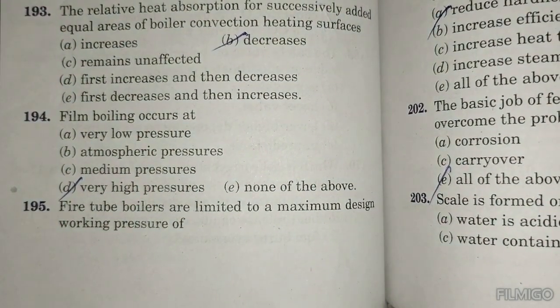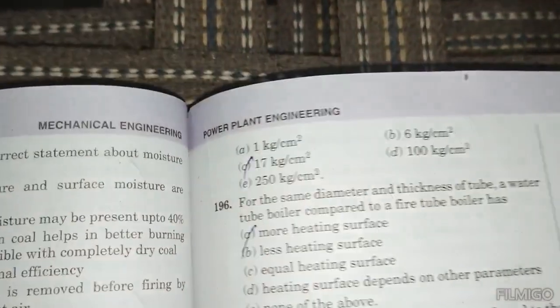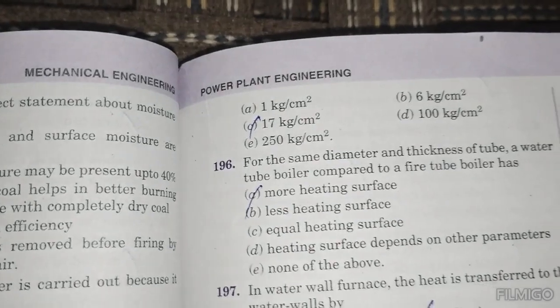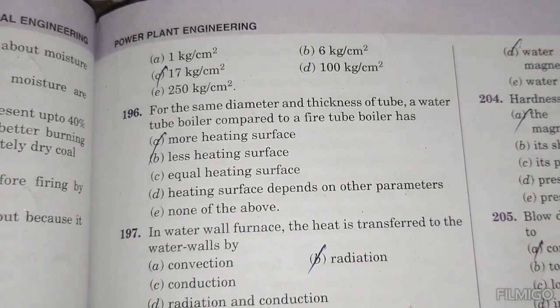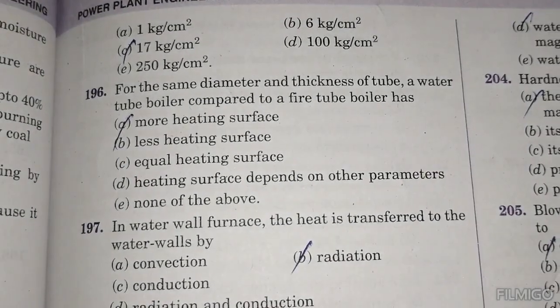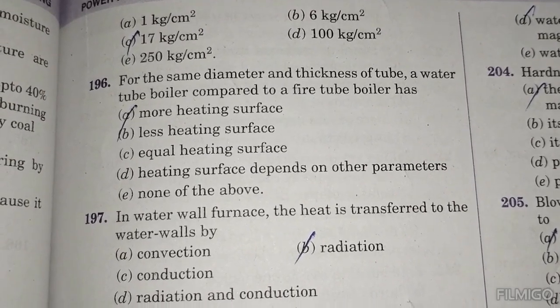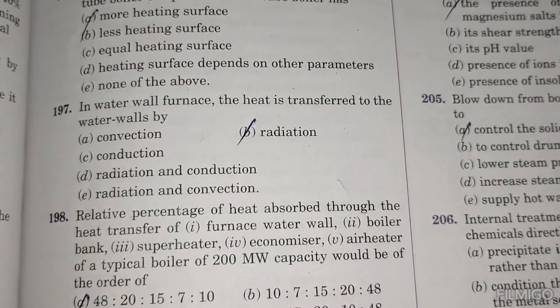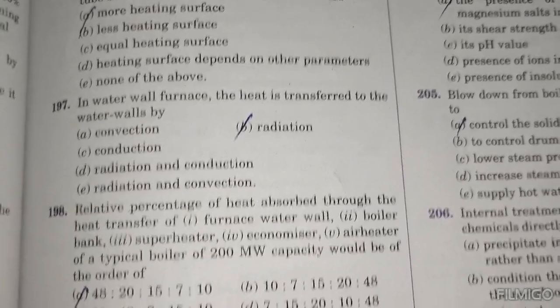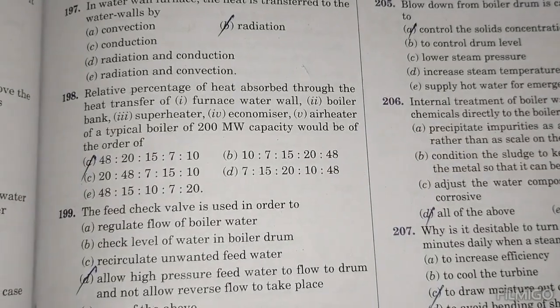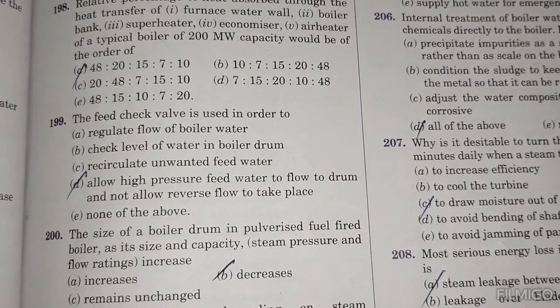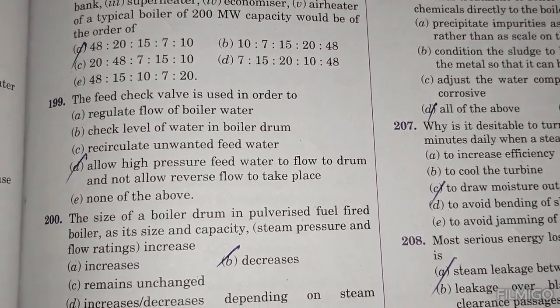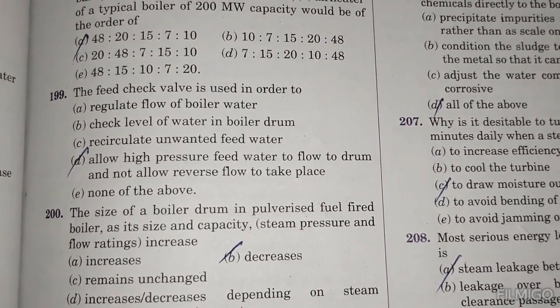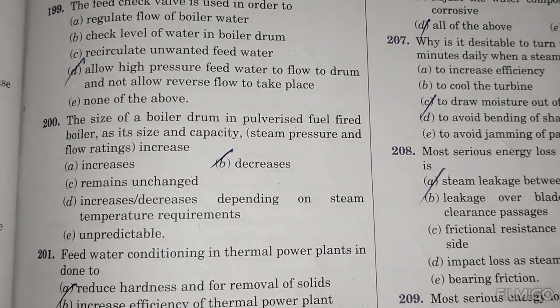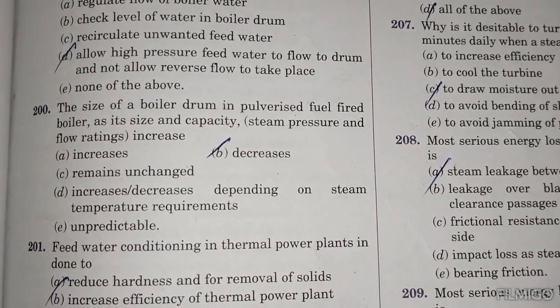Fire-tube boilers are limited to a maximum design working pressure of 17 kg/cm². For the same diameter and thickness of tube, a water tube boiler compared to a fire-tube boiler has more heating surfaces. In a water wall furnace, heat transfer to the water walls is by radiation. The feed check valve is used to allow high pressure feed water to flow to the drum and not allow reverse flow to take place. The size of the boiler drum in a pulverized fuel fired boiler decreases as its capacity increases.